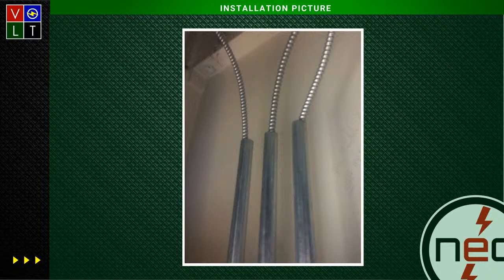I ended up not even messing with that, I just ran a new pipe out of the panel because it was way easier. I didn't want to deal with that, so I left it. That is actually a code violation, but they could have supported those within 12 inches of where it enters that sleeve, and that could be a compliant installation. It was just kind of one of those things.